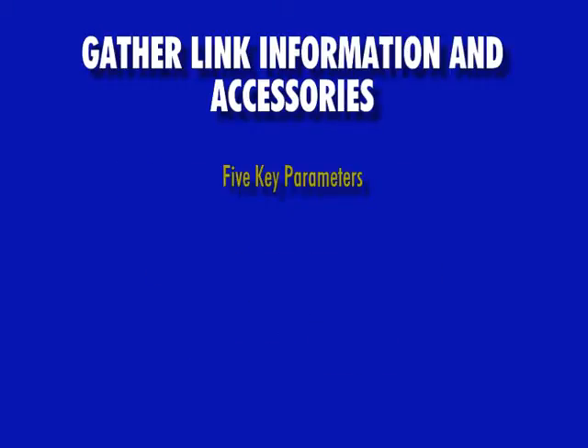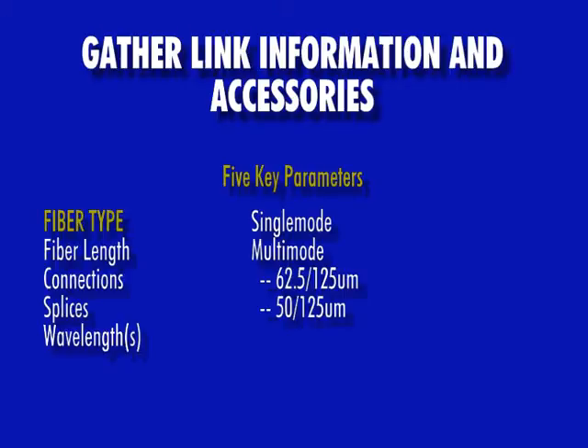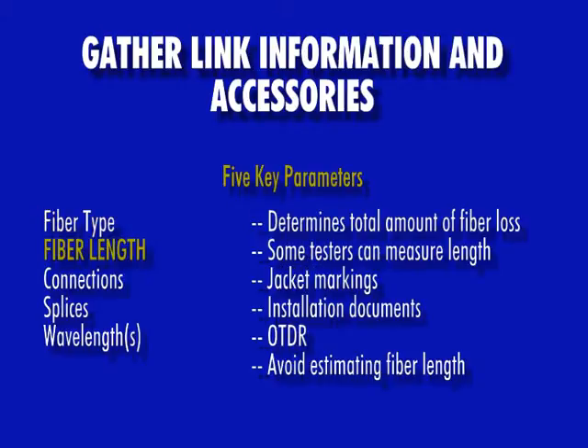There are five key parameters that apply to any fiber optic test. First is the fiber type, which will be either single mode or multi-mode — in the case of multi-mode, either 62.5 or 50 micron. Next is fiber length; it is important to know how much fiber is in the link to determine acceptable loss. Some OWL testers can measure end-to-end length automatically, including the Fiber OWL 4. Otherwise, use jacket markings, installation documents, or OTDR. Avoid estimating fiber length whenever possible.